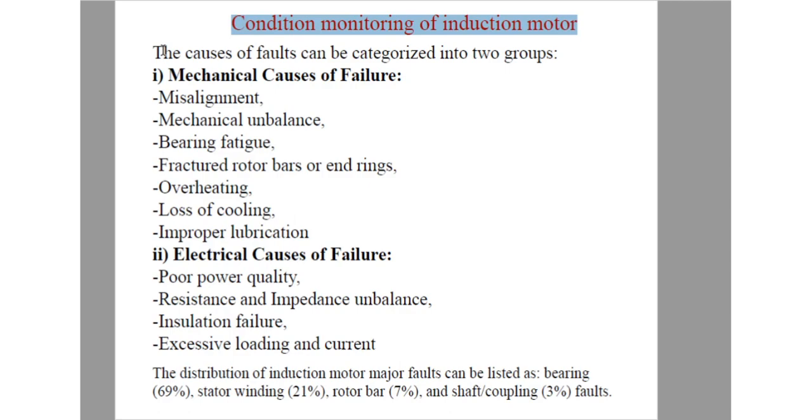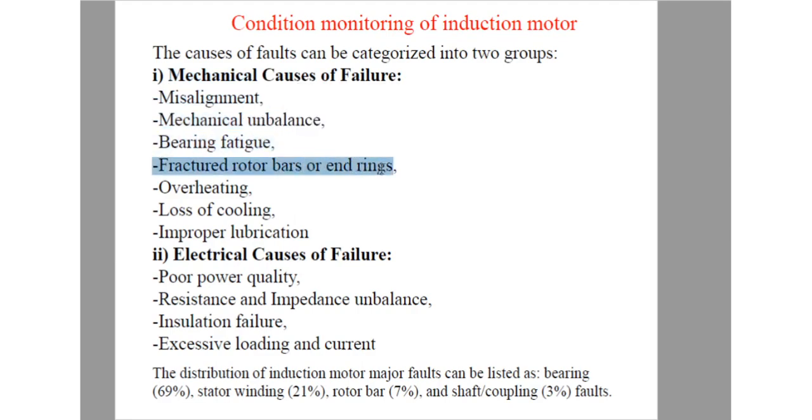The causes of failure of the mechanical components are misalignment, mechanical unbalance, bearing fatigue, fractured rotor bars or end rings, overheating, loss of cooling and improper lubrication.